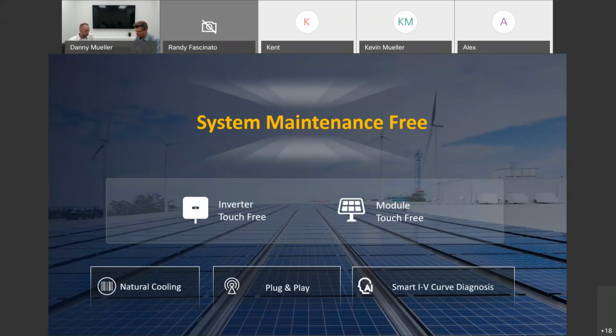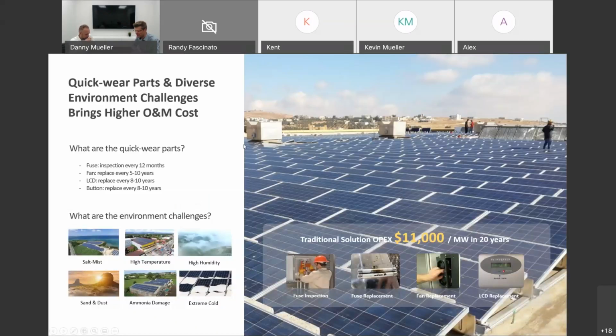If you can have such an inverter, that is so valuable, and that's more value than a cent saved here or something back and forth. It's really the peace of mind that the asset you deploy is just operating without you losing any sleep over it. And that's the core strength of the Huawei 45 KTL, because it is extremely robust. And the main reason why that's the case is the clear focus on taking everything out which is not needed and is known to have failures in the field.